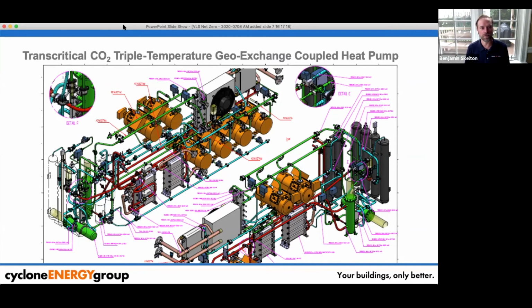When we studied energy efficiency on this and other projects, we found that a geo-coupled, geo-exchange coupled VRF system can have one of the most outstanding coefficients of performance of any system I've ever seen. So with this Walgreens project, we designed something that, to my knowledge, has never been designed or built before, and hasn't been since. These machines have existed, but never coupled to ground source. This is a transcritical CO2 triple temperature geo-exchange coupled heat pump.